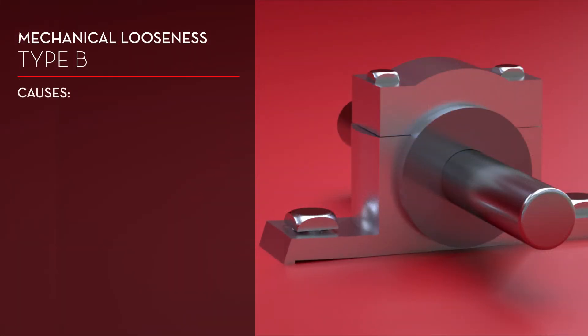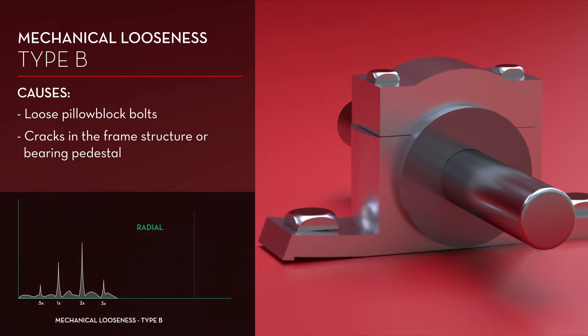Type B is generally caused by loose pillow block bolts, cracks in the frame structure, or bearing pedestal. Type B appears on the spectrum as two pulses per revolution with some floor noise.